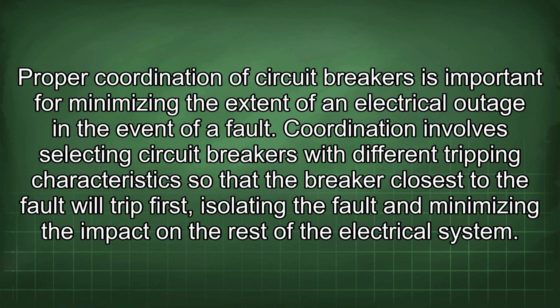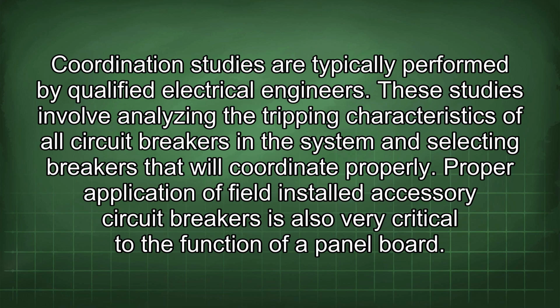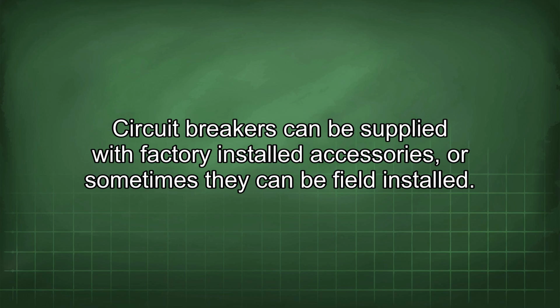Coordination involves selecting circuit breakers with different tripping characteristics so that the breaker closest to the fault will trip first, isolating the fault and minimizing the impact on the rest of the electrical system. Coordination studies are typically performed by qualified electrical engineers. These studies involve analyzing the tripping characteristics of all circuit breakers in the system and selecting breakers that will coordinate properly. Proper application of field-installed accessory circuit breakers is also very critical to the function of a panelboard. Circuit breakers can be supplied with factory-installed accessories, or sometimes they can be field-installed.